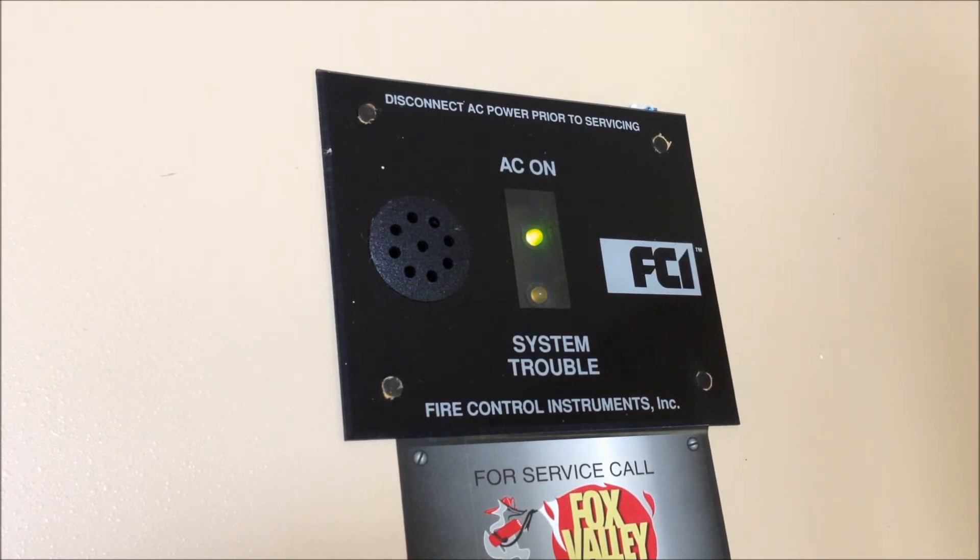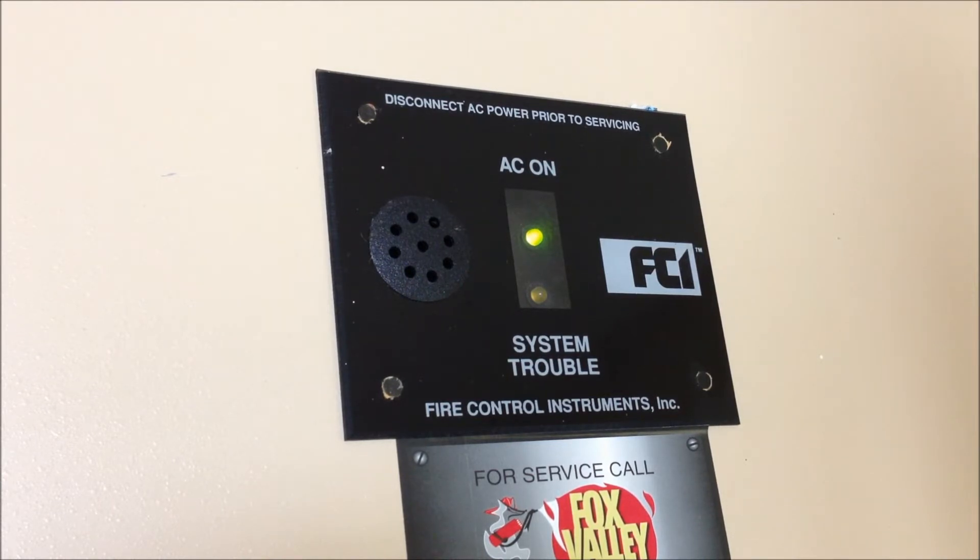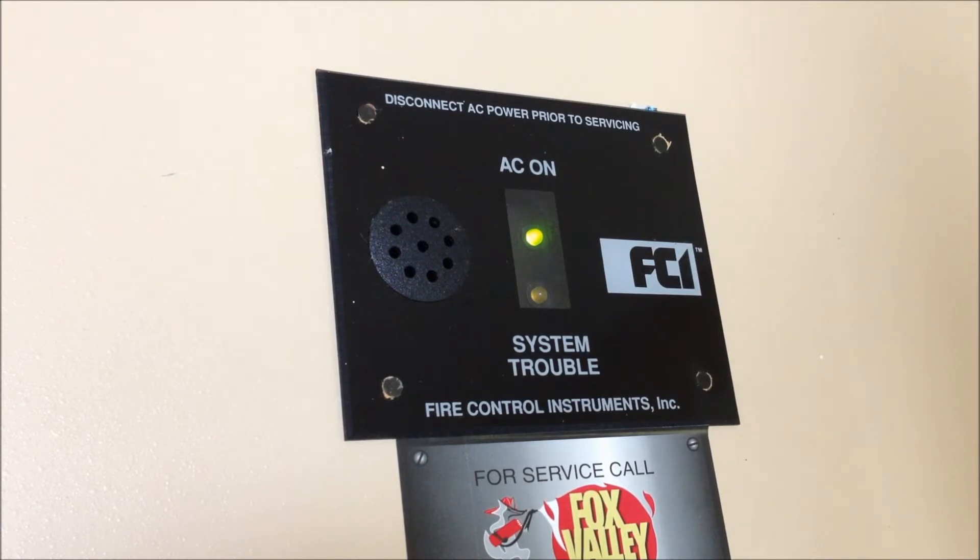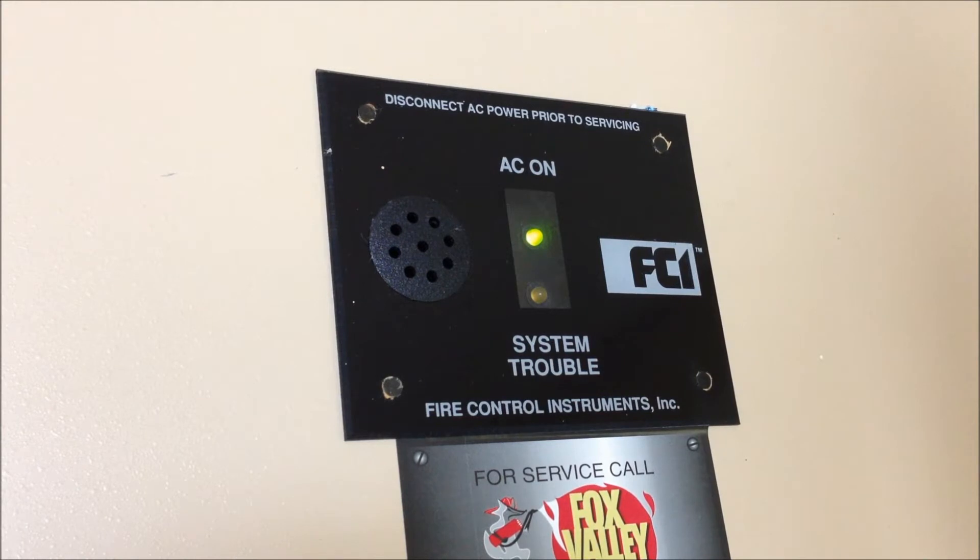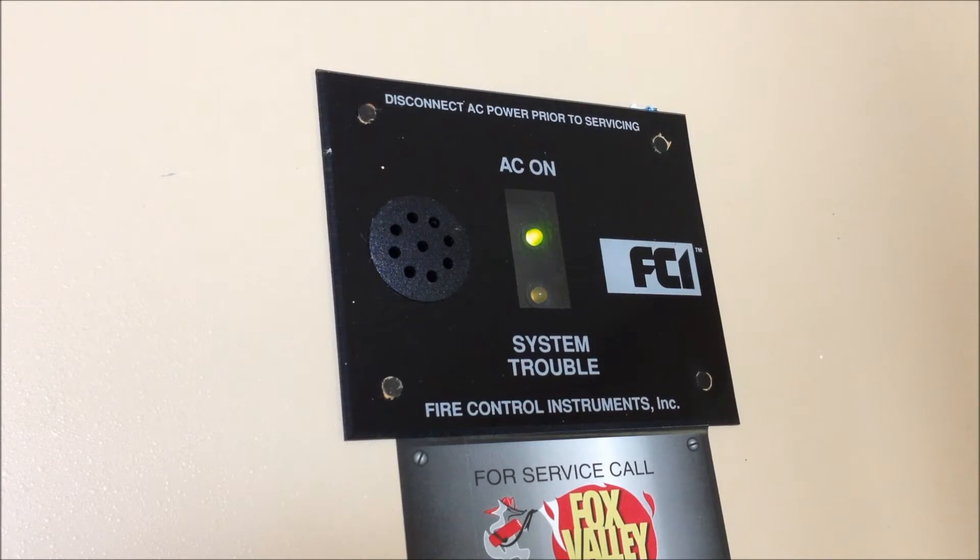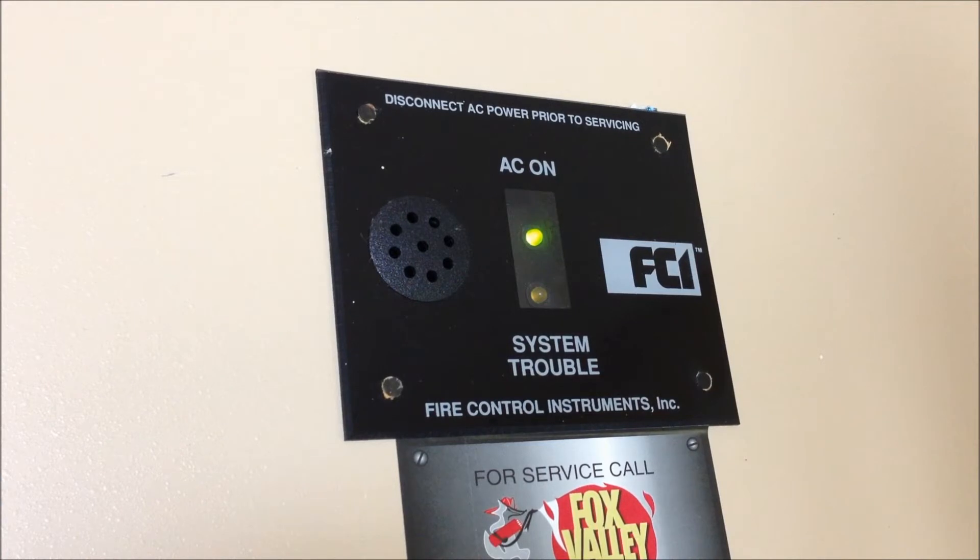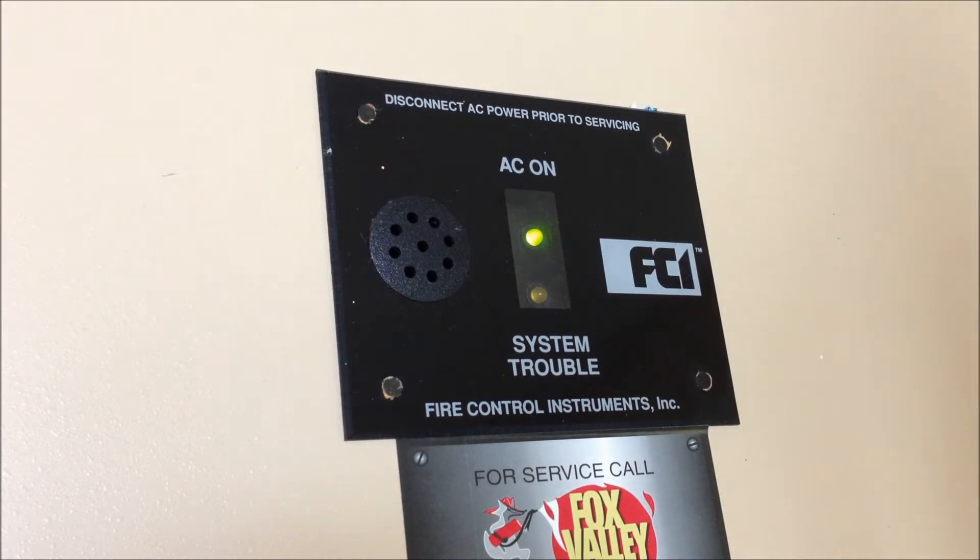So this panel was manufactured and installed in 1994. It was installed in a bank building just a little bit south of where I live on a relatively small system with five pull stations and five horns, two of which had strobes installed on them, so three horns and two horn strobes, and it was a two-story building. This is a four zone panel although it is installed in the larger 12 zone cabinet. So let's pop it open and take a look at the inside.